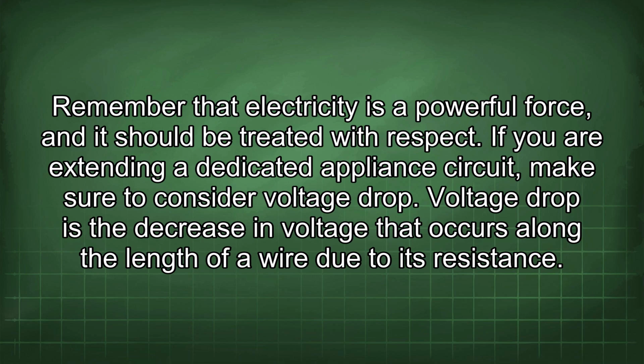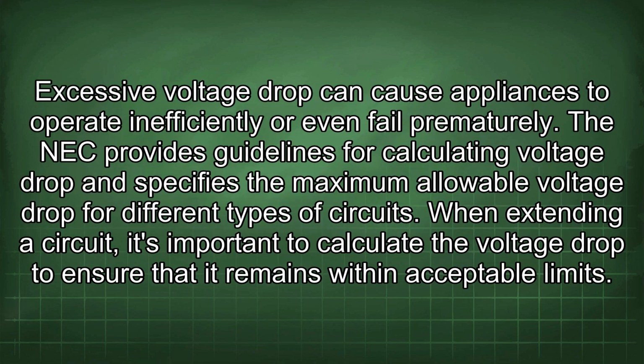If you are extending a dedicated appliance circuit, make sure to consider voltage drop. Voltage drop is the decrease in voltage that occurs along the length of a wire due to its resistance. Excessive voltage drop can cause appliances to operate inefficiently or even fail prematurely. The NEC provides guidelines for calculating voltage drop and specifies the maximum allowable voltage drop for different types of circuits.